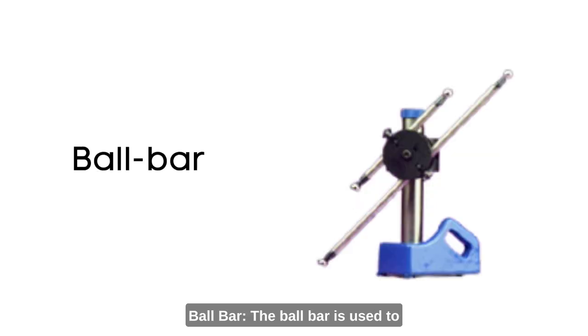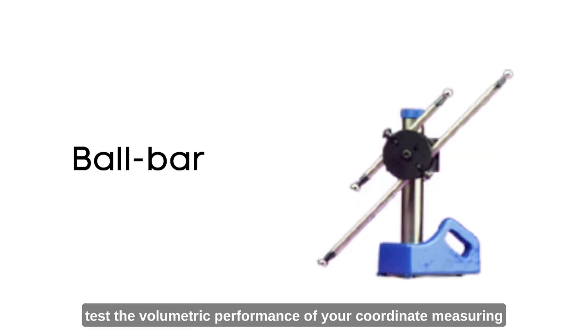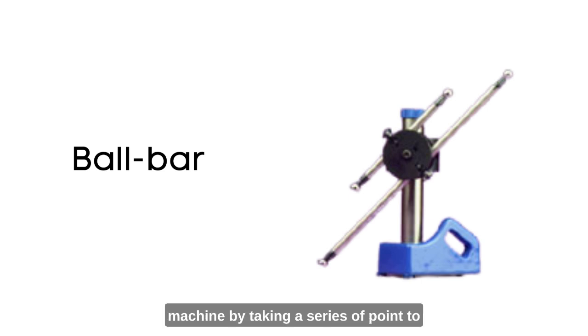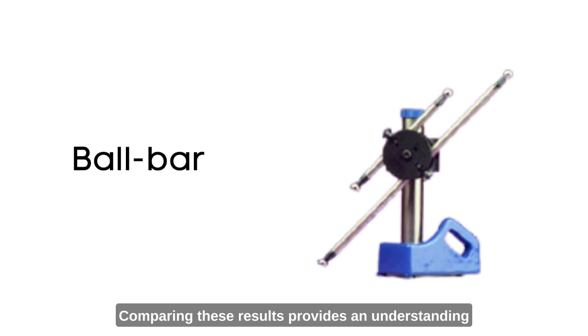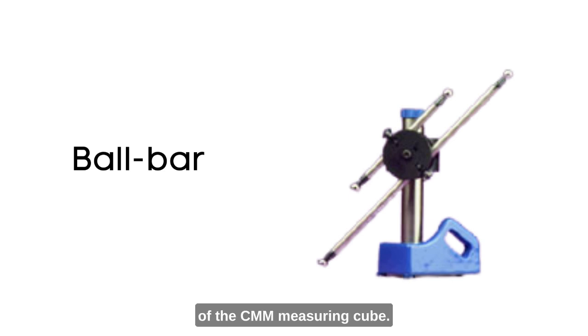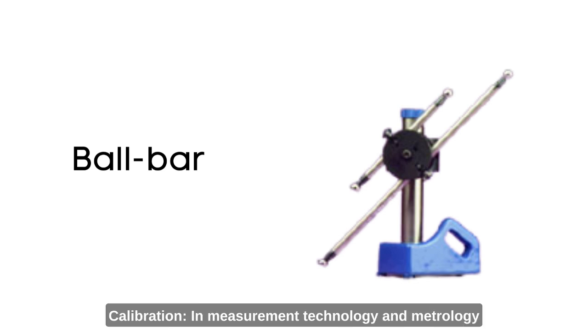Ball Bar: The ball bar is used to test the volumetric performance of your coordinate measuring machine by taking a series of point-to-point distances in reference locations. Comparing these results provides an understanding of the CMM measuring capability.